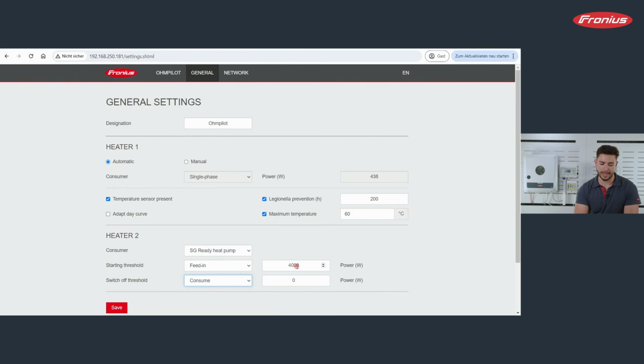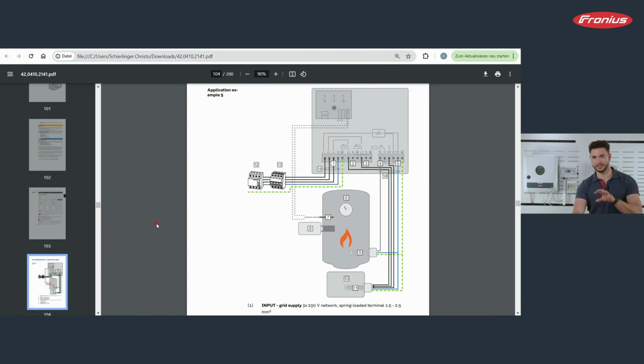Very simple. And I haven't mentioned that the connection I was talking about, the 2-pole cable, is connected on our multifunctional relay that we have seen earlier. For that matter, I can highly recommend checking out a sketch that we have in our manual. For example, here would be an application example with 2 heating rods. One heating rod is single phase connected in our boiler. The second one is 3-phase connected in our puffer tank, for example. Or it could also be in the same boiler, doesn't matter.